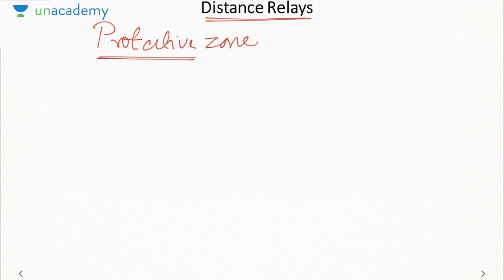Next type of relay is called as distance relay. Now as the name suggests, distance relays are the relays which operate if the fault occurs within certain distance of the relay, and we call such a distance as protective zone. If fault occurs within the protective zone, the relay will operate.